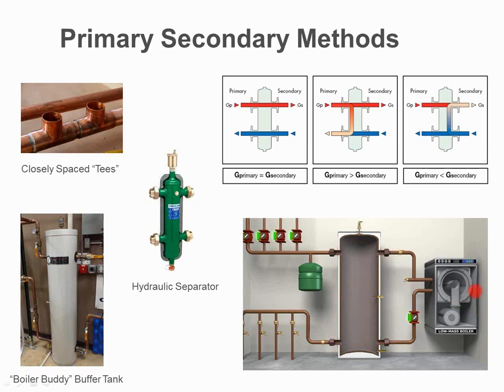So now our boiler does not cycle as much because instead of seeing little zones, it's seeing 30, 40 gallons, whatever the buffer tank is designed for. That's where we're going to store our BTUs. These buffer tanks are super insulated. Even if they're running 180 degrees, you can have your hand on them all day long. So we're not losing energy from them. It just makes that boiler run longer when it needs to and cycle a lot less often.